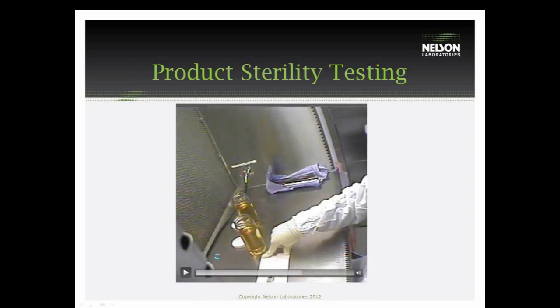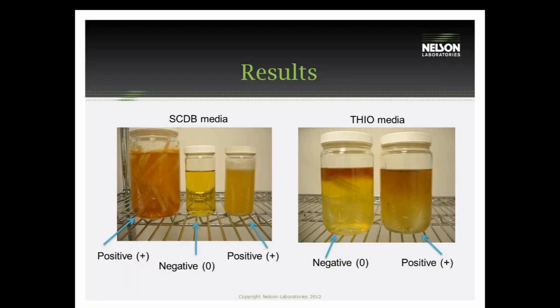Following the testing, we will score the jars for growth. You can see from the slides what a positive would look like for each media type. We are looking for no growth here. What we need to accomplish for a batch release is complete kill on the half cycle, so any growth in the media is going to directly impact the batch release — it will stop it in its tracks. We definitely need no growth here.